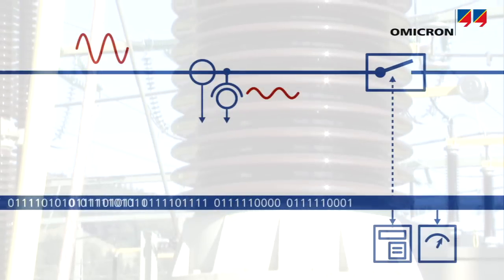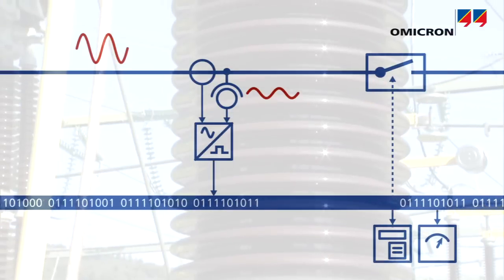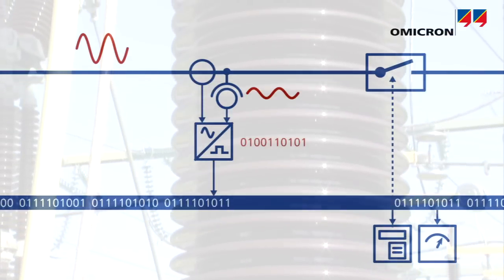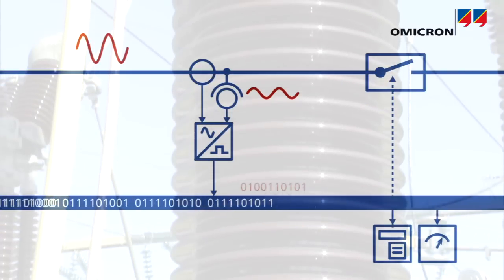From instrument transformers or sensors, a merging unit collects the measured values, merges these sampled values into a data stream belonging to one feeder, and publishes them to the substation network.